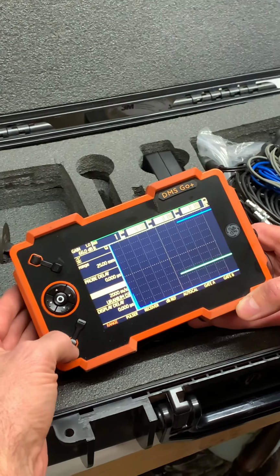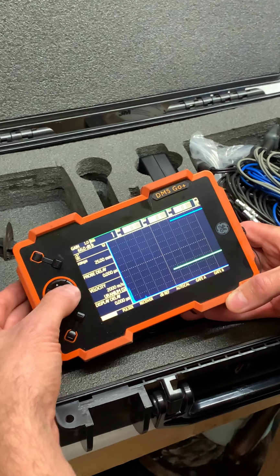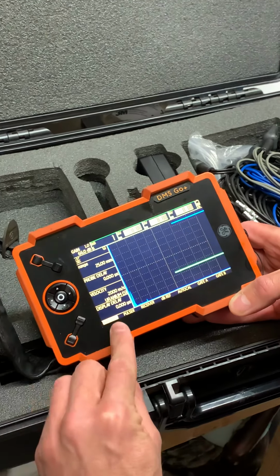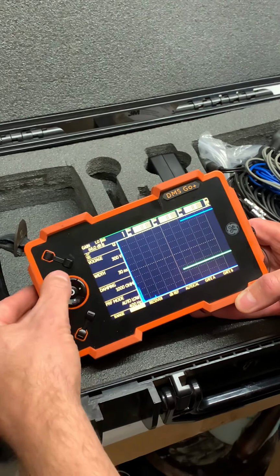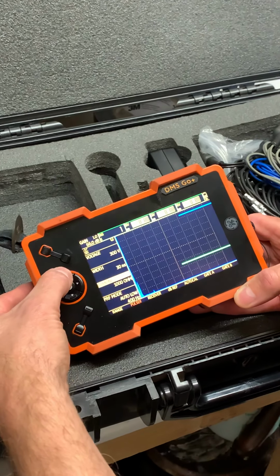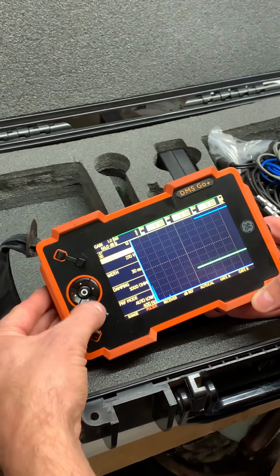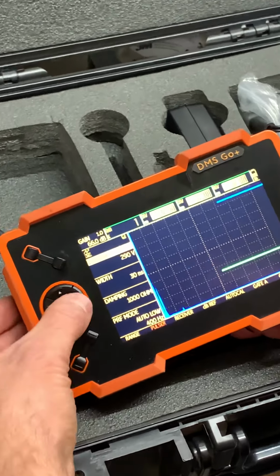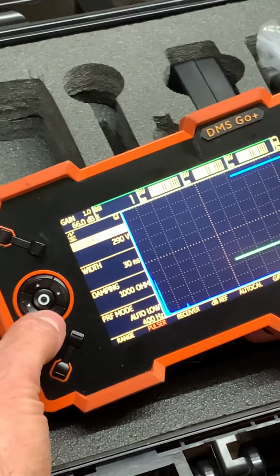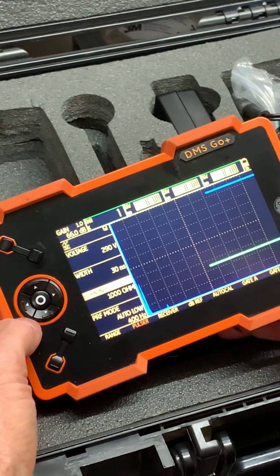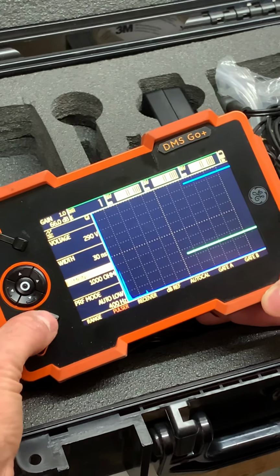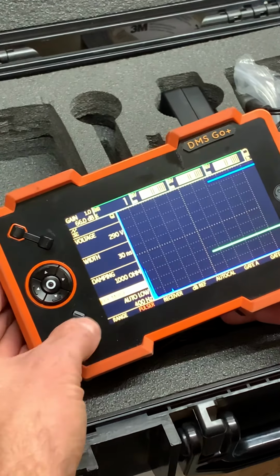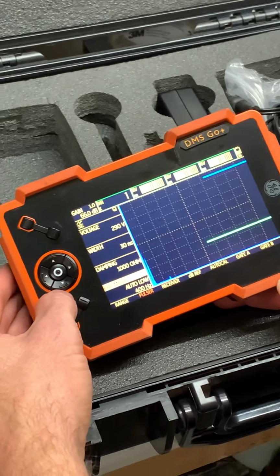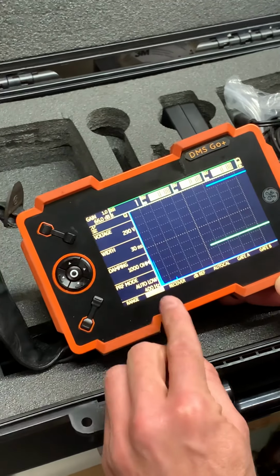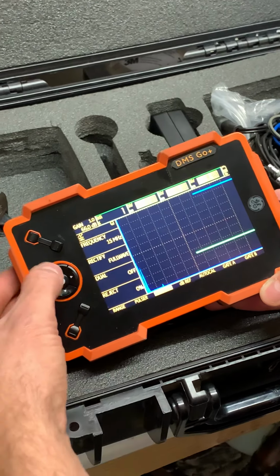Now if I come down to the bottom and move along, range is highlighted, I go to pulser, I can go up into that and change my pulser voltage using either of the arrow keys or the rocker. I can change my damping, 50 ohms or 1000 ohms. I can change my PRF, or come down again to pulser and move across to my receiver menu.